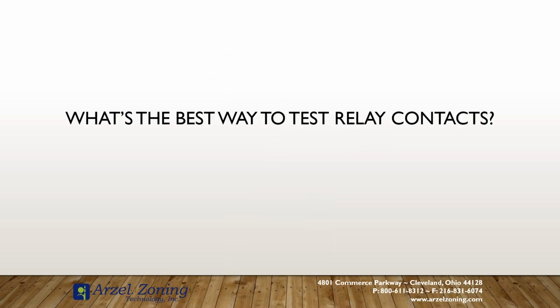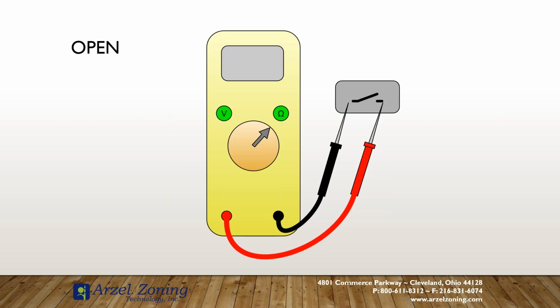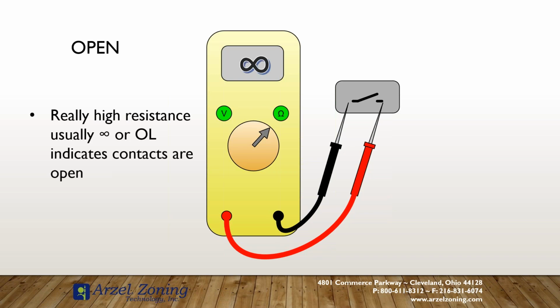All right, well, what is the best way to test a relay? What's the best way to test the contacts on a relay? Ohm meter, resistance. The best way to test the contacts on a relay are to test your ohms. If I have a set of open contacts, what am I going to read? Right. We'll read infinity. We'll read high resistance. We'll read OL, or possibly that little infinity symbol. And that indicates an open set of contacts.